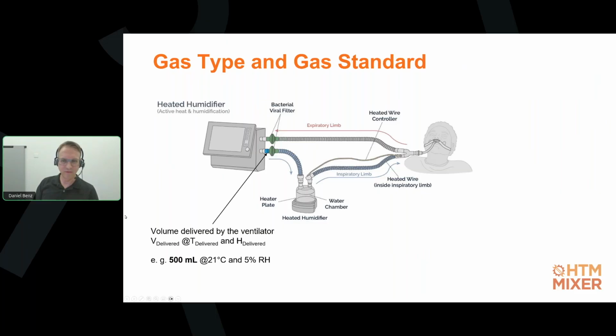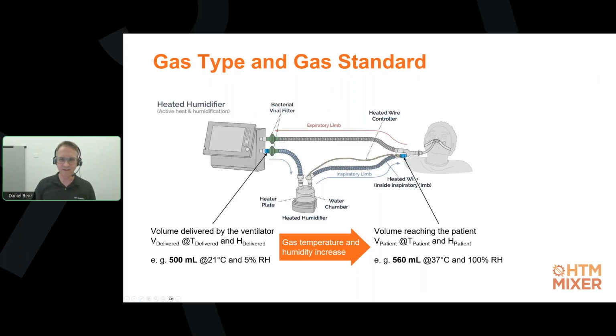What happens to that volume of gas while it travels along the inspiratory limb until it actually reaches the patient? Because we have a humidifier and a heated wire, a heated limb, the gas temperature and humidity are going to increase. And what is the consequence, based on what we've learned in our earlier slides? The volume is going to increase as well. So in our example, the volume that actually reaches the patient is no longer the 500 milliliters that the ventilator delivered, but approximately 560 milliliters, because the gas temperature at the Y piece is 37 degrees Celsius and the gas humidity is 100%.